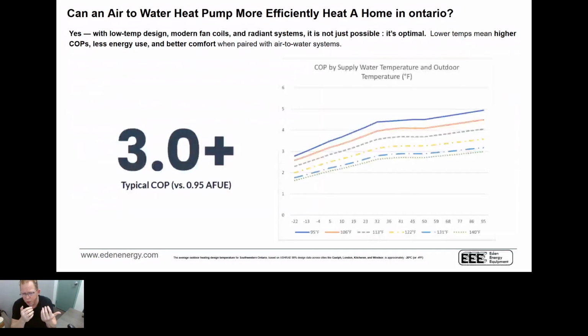Really, what's cool about an air to water heat pump, and this is a graph that shows the different COPs at different temperatures, and where air to waters are really slick is that we have the opportunity to choose what we're going to do inside the space. Typically, if we were going to do a boiler, we do a radiant floor heating system. We're going to hold that slab at 84, 85 degree surface temperature. What that means is that we can easily achieve a COP of 3 the bulk of the year. And these different lines are representing COPs at different temperatures. I'm going to call out one in particular that I want you to look at. If we look at -4 degrees Fahrenheit, this blue line at 95 degrees Fahrenheit means at design, so the degree design day, we could maintain a COP of 3.1.